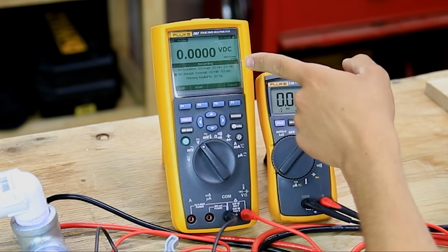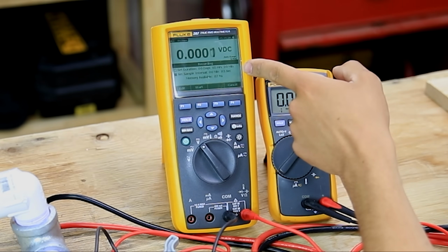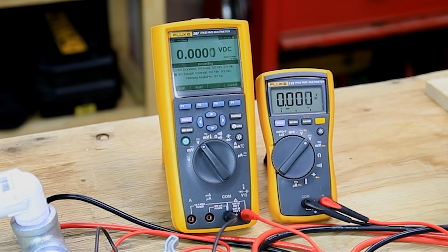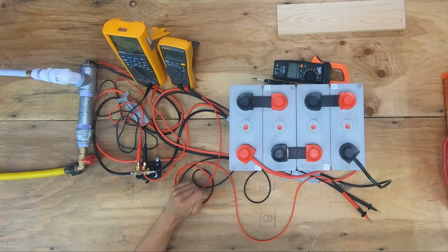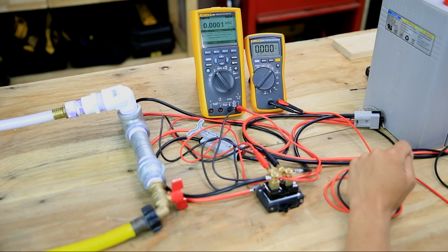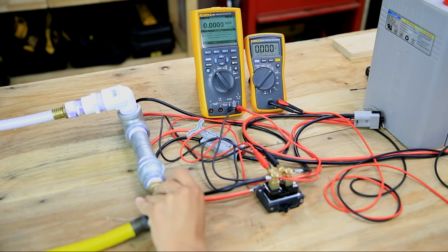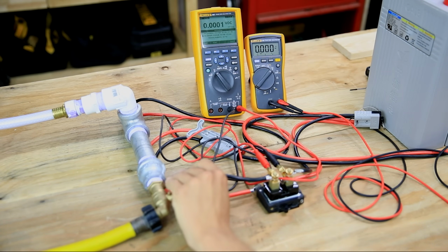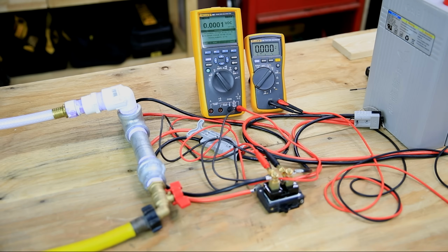I have it set to make a 5 hour and 30 minute recording with a sample every 3 seconds. I have 87% memory available on this meter, so I should have plenty of storage to do this test. I'm going to go ahead and turn on the water to my test load, and now that we have water flowing, we're ready to begin the test.